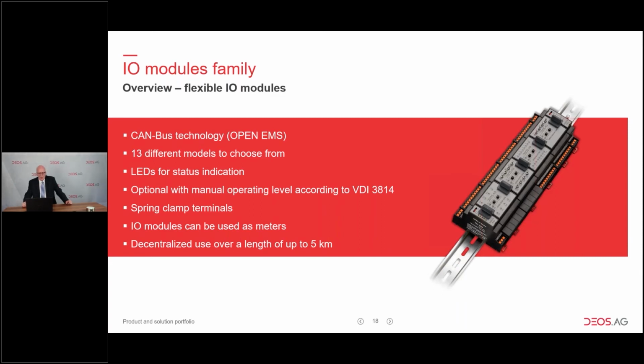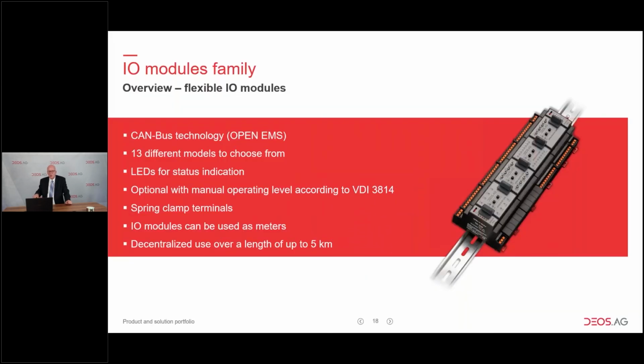We also have spring clamp terminals for very easy installation, and optionally a manual operating level according to German VDE 3814. This manual operating level is a question of comfort for commissioning projects, allowing you to prove the function of a pump or valve directly via this manual operating level.